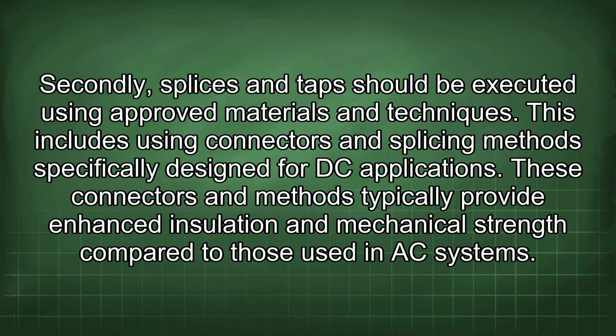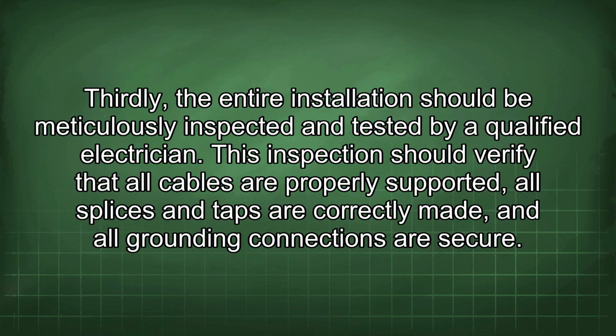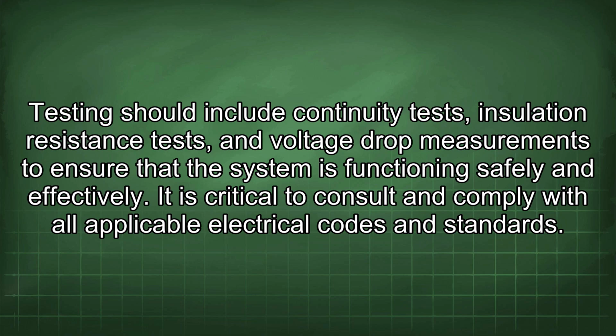Secondly, splices and taps should be executed using approved materials and techniques. This includes using connectors and splicing methods specifically designed for DC applications. These connectors and methods typically provide enhanced insulation and mechanical strength compared to those used in AC systems. Thirdly, the entire installation should be meticulously inspected and tested by a qualified electrician. This inspection should verify that all cables are properly supported, all splices and taps are correctly made, and all grounding connections are secure. Testing should include continuity tests, insulation resistance tests, and voltage drop measurements to ensure that the system is functioning safely and effectively.